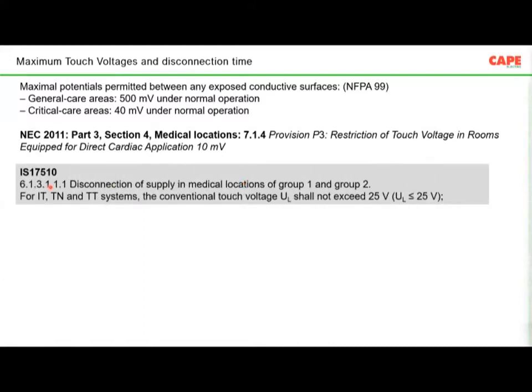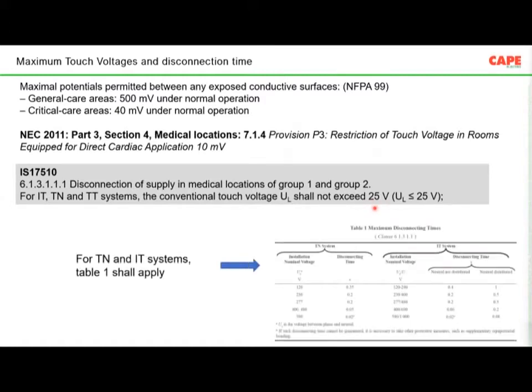Similarly, the new medical location standard, IS 17510, 2020-21, clause number 6.1.3.1.1.1, disconnection of supply in group 1 and group 2 medical locations. The standard says the conventional touch voltage shall be lesser than 25 volt. Conventional touch voltage is not in normal condition; this is in a fault condition. That means probably you have a faulty equipment or faulty electrical wiring. Under a fault condition, the maximum allowed touch voltage in group 1 and group 2 medical locations is lesser than 25 volt, or before the voltage reaches 25, we are supposed to disconnect the supply.